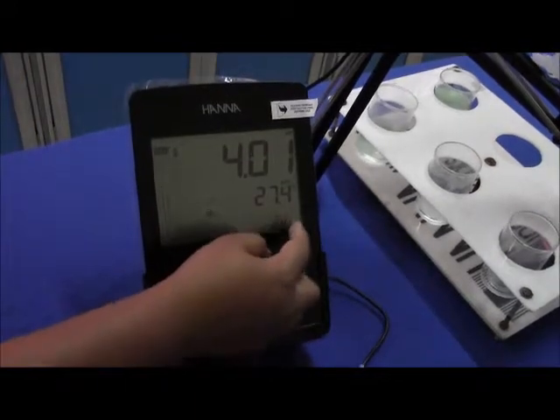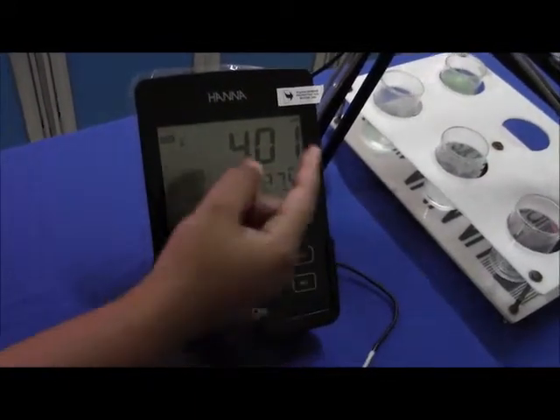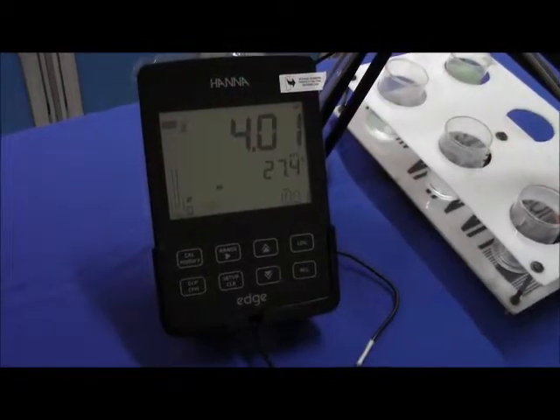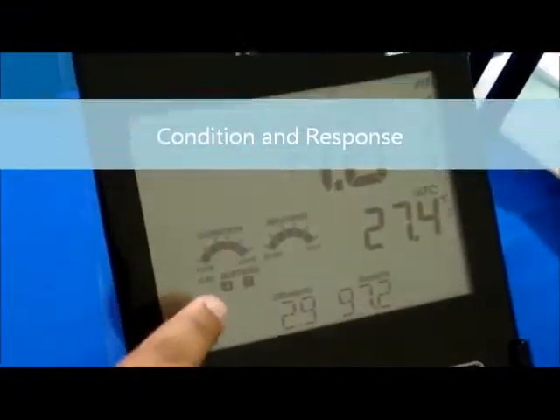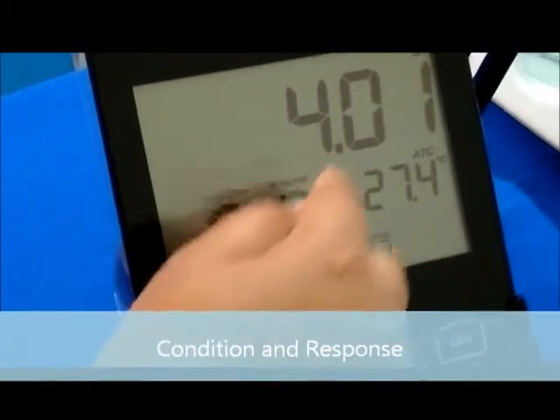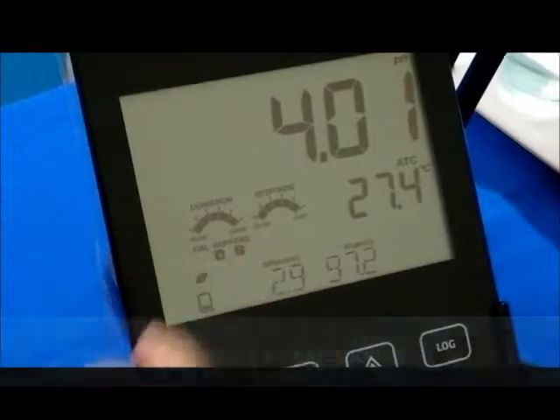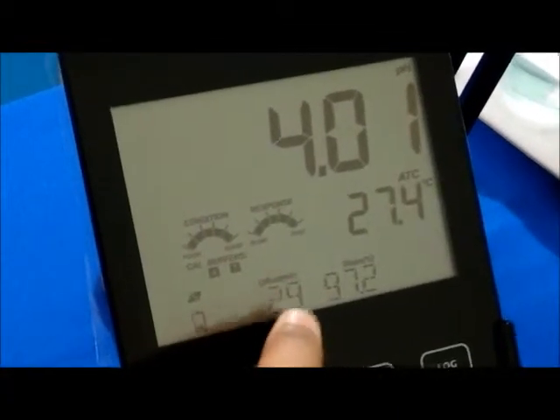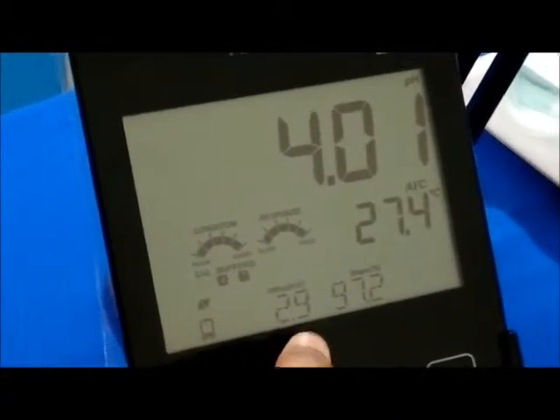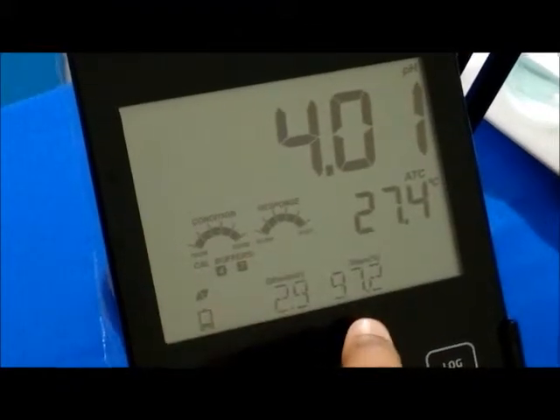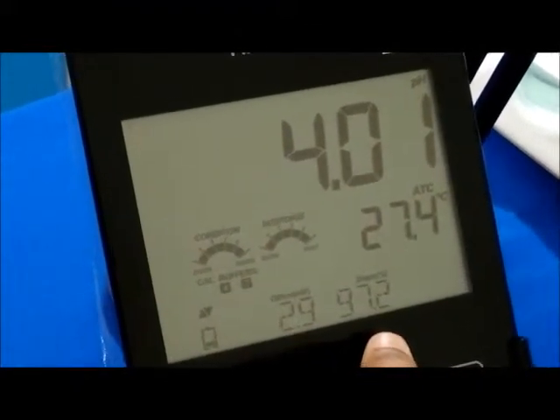Now it is asking for 10.01. If you wish to calibrate the meter for 10.01, you can again immerse the electrode into 10.01. After calibration, the meter is showing the probe condition, which is 100%. It is showing the response of the meter along with the probe, which is again 100%. Here you have your offset value, which should be plus or minus 10 mV, and your slope percentage should be around 90 to 100%. Now we can directly take the sample readings.